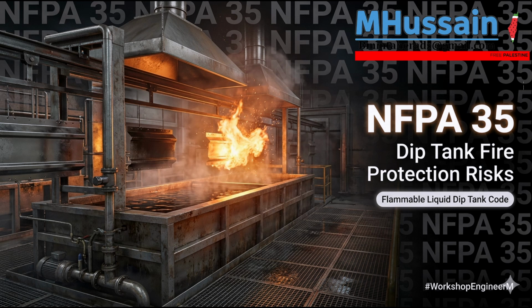It illustrates how deeply the chemical engineers must collaborate with the safety engineers just to dump a bag of pigment. And they have to be in constant communication. And what about the physical mechanics of liquids falling through the air? The standard has a specific section on fill pipes. Yes, Section 9.5.3 addresses a phenomenon known as splash filling. If an operator is transferring more than 60 gallons of a non-conductive class liquid into a large tank, they cannot just open a hatch at the top and let the liquid free fall through the air.